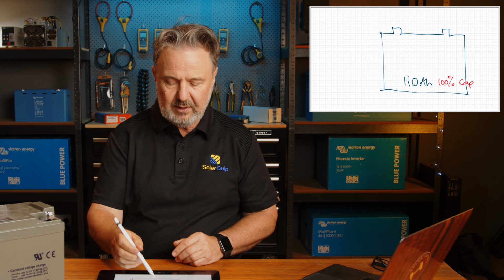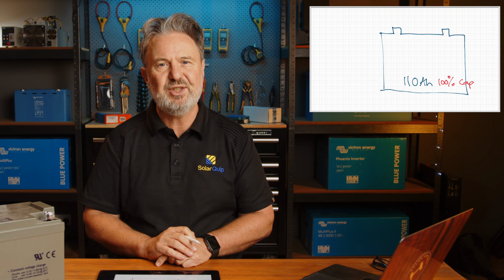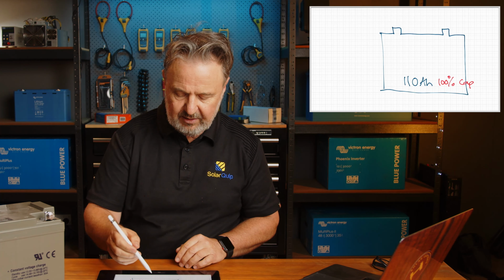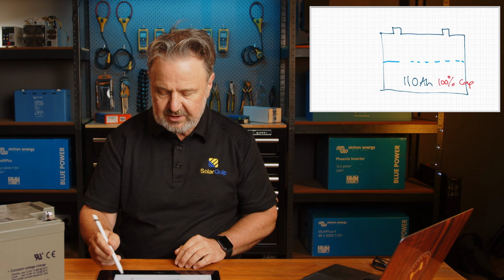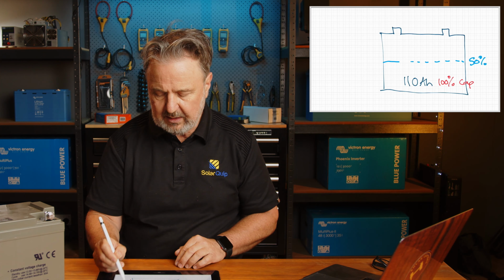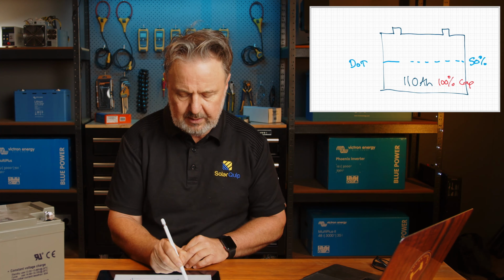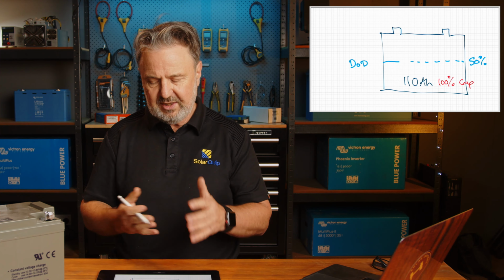So often we'll have a maximum depth of discharge set in our equipment to suit the longevity of that battery. If we call this the 50% depth of discharge, DOD for short, this is the point at which we choose not to go below on a regular basis to maximize the life of that battery. Now, I chose 50% because it's pretty common for off-grid system designs with lead-acid batteries to limit to 50% as your maximum depth of discharge. But you really do have that reserve capacity there if you needed it because of an emergency.